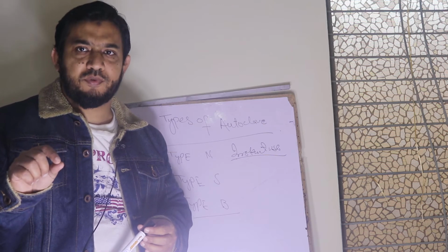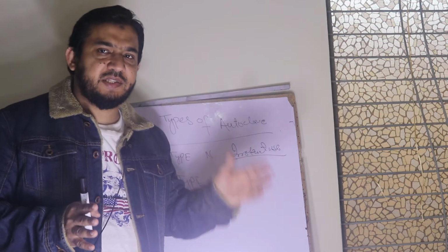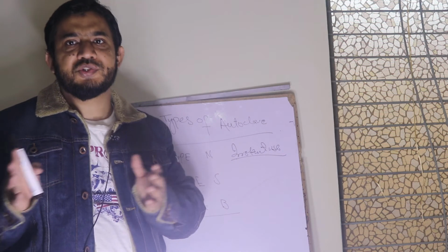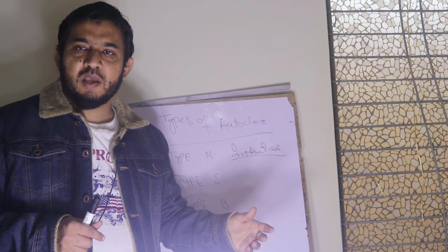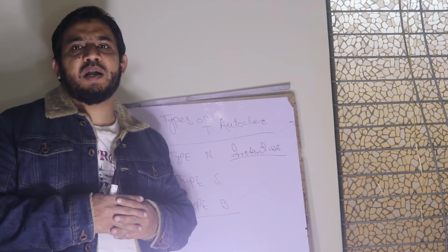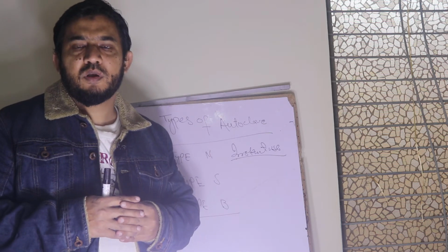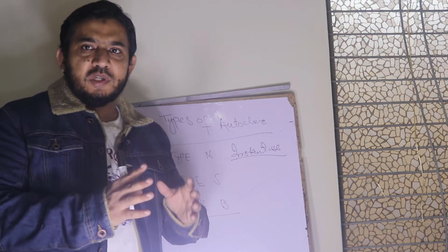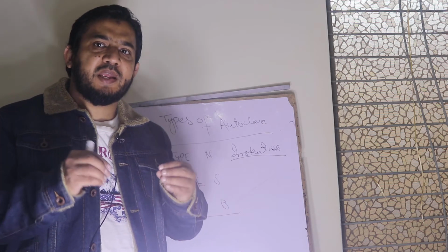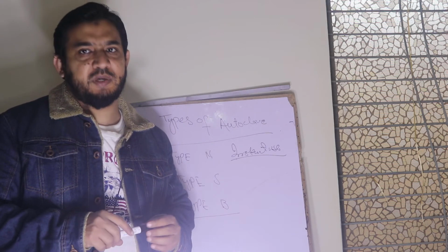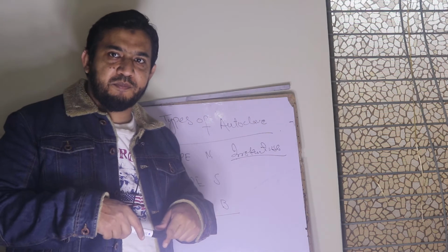In S class, we first create a vacuum in the chamber where the instruments are placed. So when we introduce the steam from the steam chamber into the sterilization chamber, the steam can penetrate deep into the instruments. So it is better than N class, in which the whole chamber was the same.